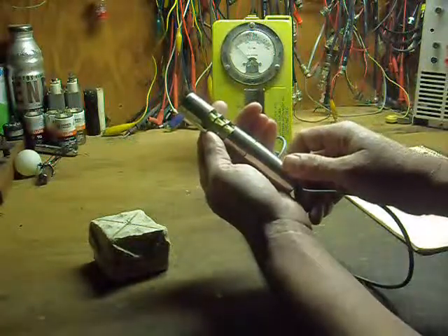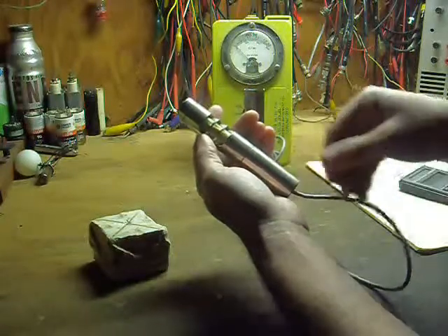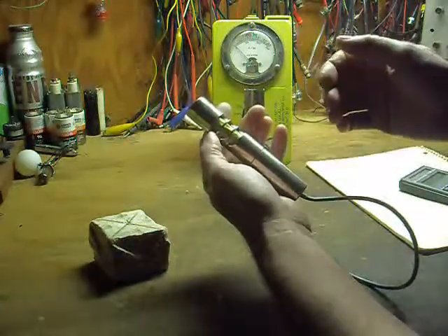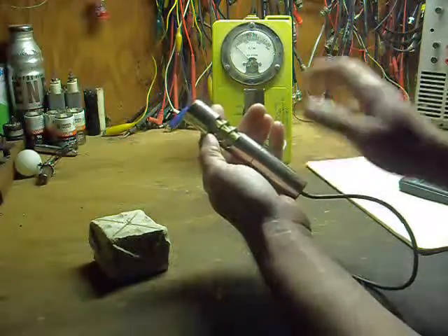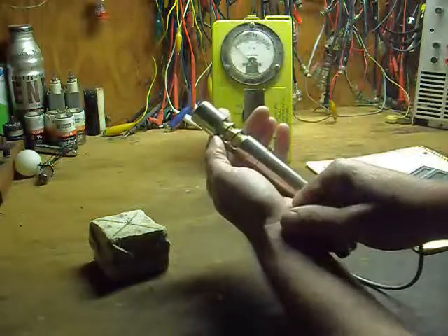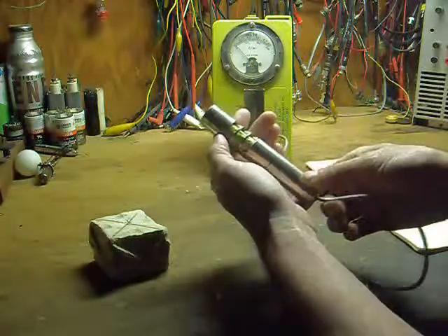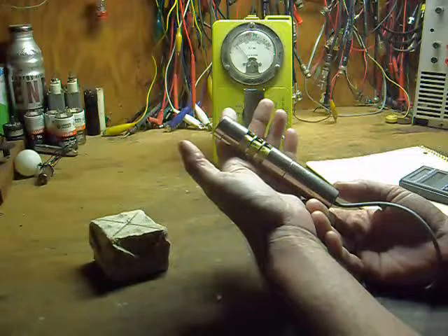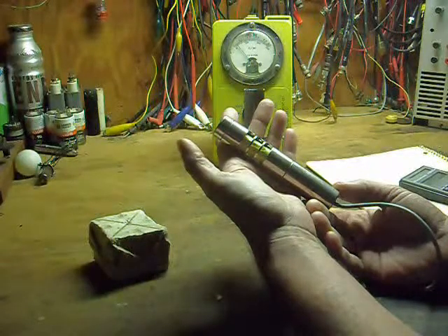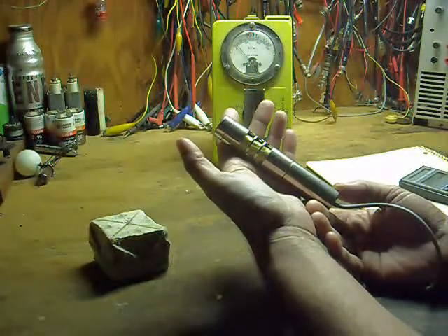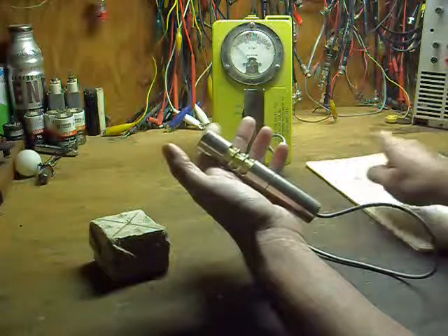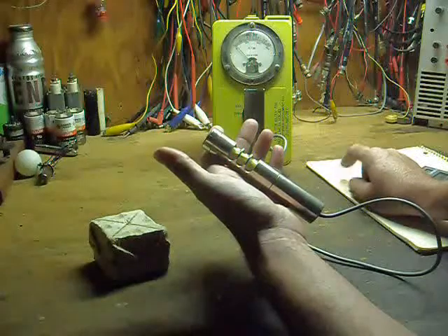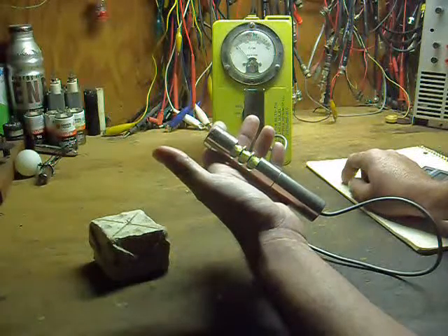The intensity of the pulse is the same no matter what the energy of the incident particle is. Therefore, it is a non-proportional counter. Because of that fact, it cannot be used to take calibrated measurements of more than one type of radiation. Its calibration only holds true for a narrow band of radiation particle energy. In general, Geiger tubes are calibrated to measure gamma radiation.